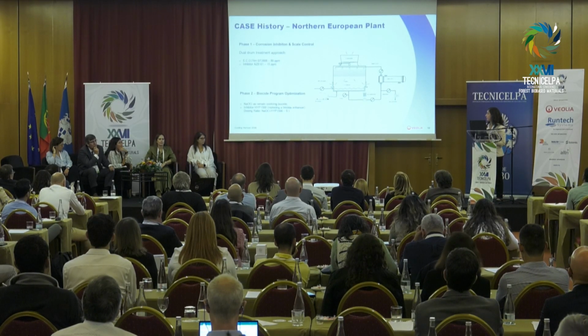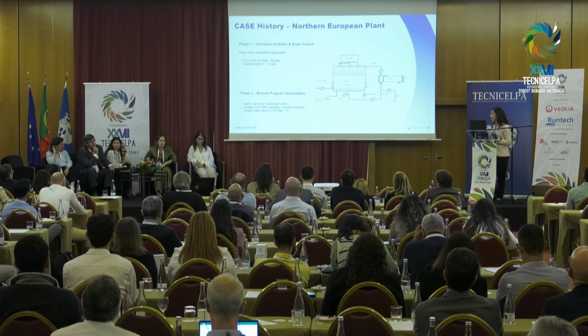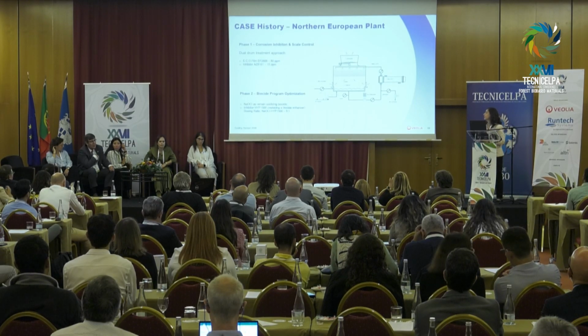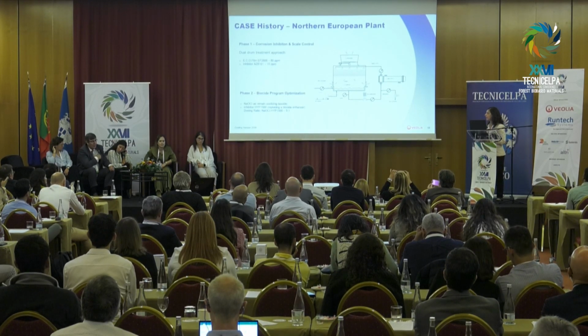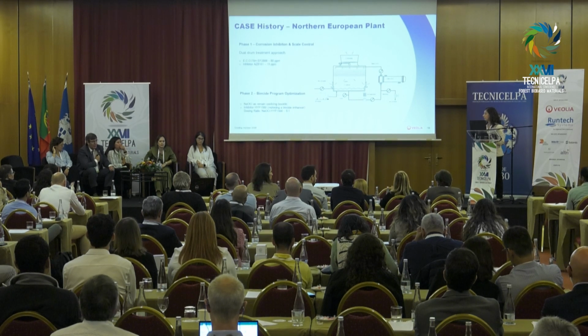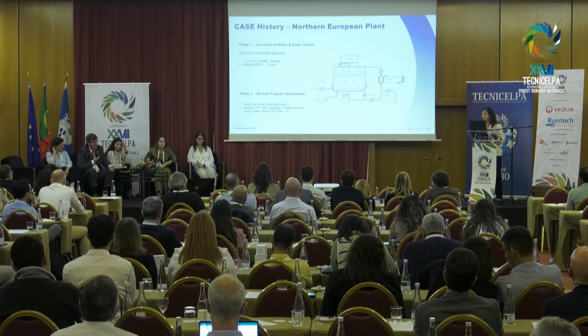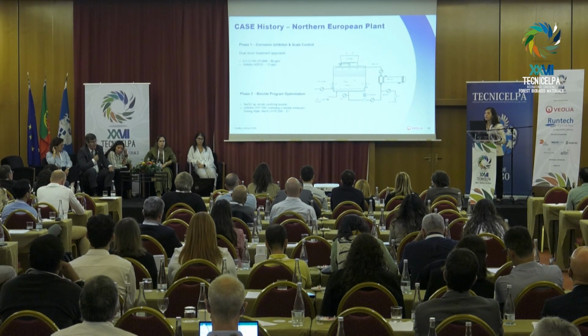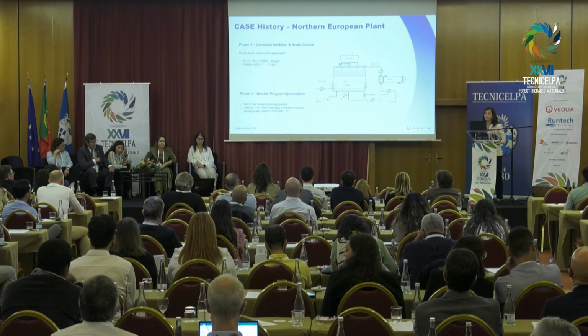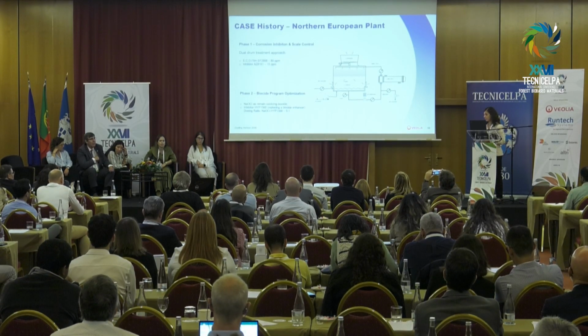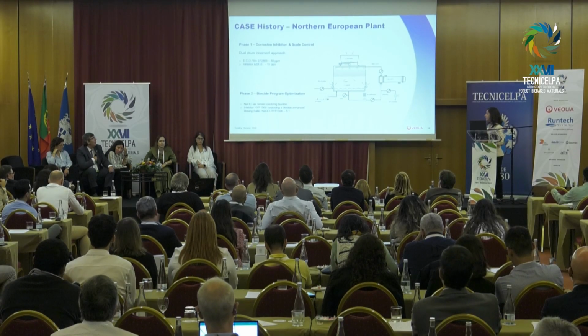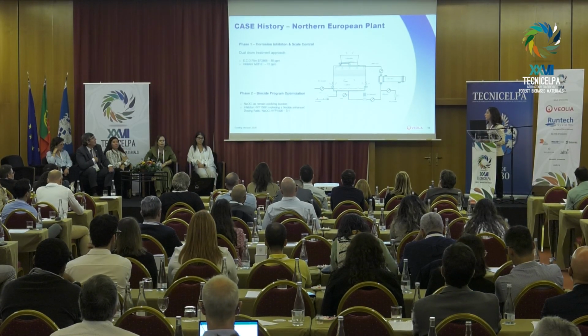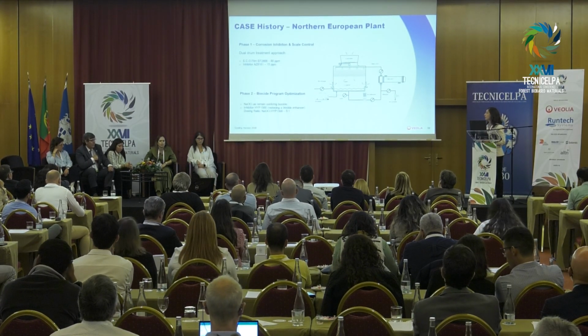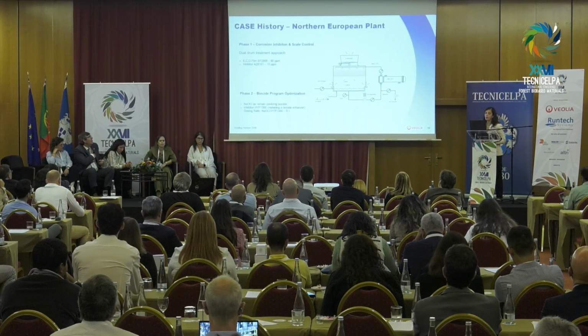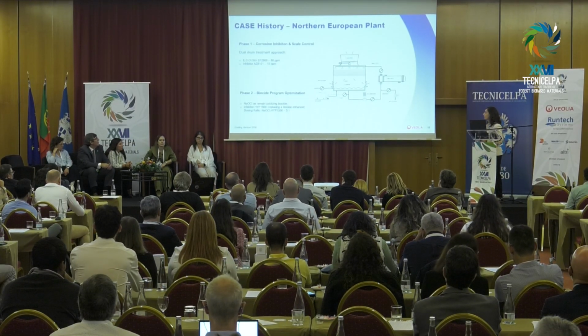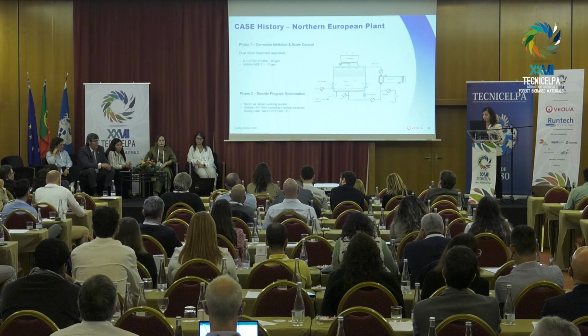In the first phase, and also in the second phase, we replaced the biocide enhancer with the technology, the inhibitor HIP 1500, which is a bleach stabilizer. It's not a biocide, it's not a biodispersant, it's a bleach stabilizer. It's dosed in proportion: for each 5 ppm of sodium hypochlorite, we dose 1 ppm of HIP.